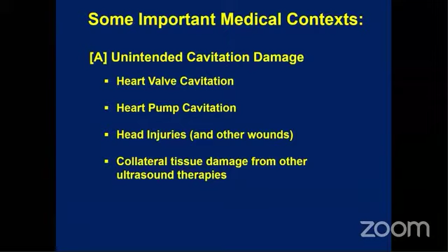The one I'm most familiar with is heart valve cavitation. Heart valves do cavitate somewhat. Artificial heart valves cavitate a lot. And that's been a significant problem, because the cavitation in artificial heart valves, and I'll show you there's a whole range of designs, causes not only damage to the valve itself, though that's a relatively minor issue, but also they destroy red blood cells at sometimes an unacceptable rate.